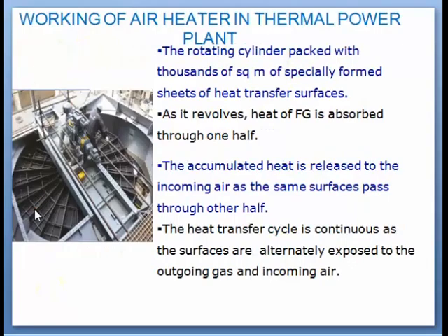So here you can see this is the storage media, this rotating cylinder which rotates at very slow RPM, and this is packed with this type of heat absorbing material. Just like you can imagine the fins in a car radiator. So this is fully packed, which increases its surface area, and ultimately that increases the heat absorbing capacity. So the rotating cylinder is packed with thousands of square meters of specially formed sheets of heat transfer surface.